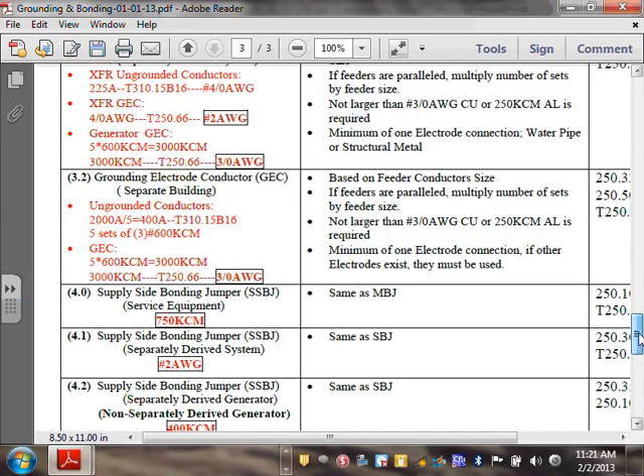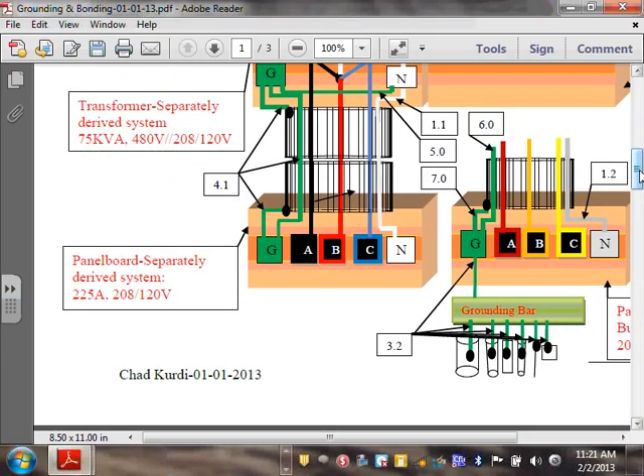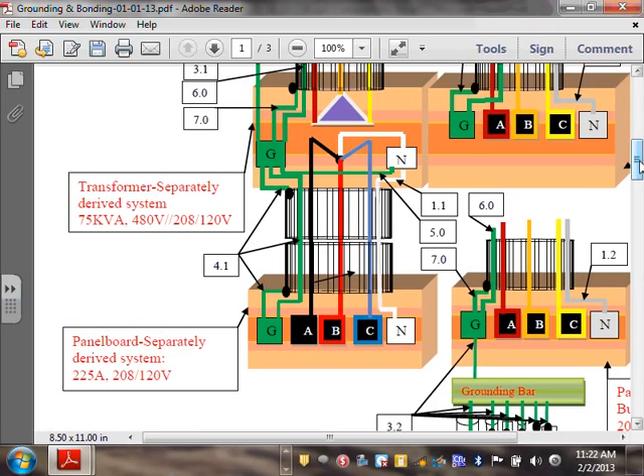And if you guys, okay, go all the way. So what I did here is I have a transformer, 75 kVA, typical transformer, and I'm landing it in a panel, 225 amp panel, typical, and the panel is 208/120, and my phase conductors, the 208 3-phase, are number 4. Then where was the main bonding jumper? The main bonding jumper, I made inside the transformer, which I have the option. If you have a separately derived system transformer, guys, you have the option.